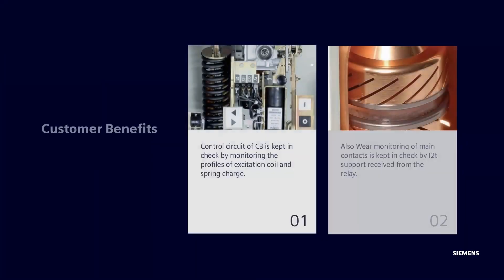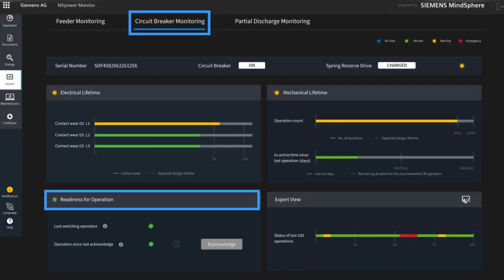As a result of the addition of the Expert View in Circuit Breaker Monitoring View, the control circuit of CB is kept in check by monitoring the profiles of excitation coil and spring charge. Also, monitoring of main contacts is kept in check by I2T support received from the relay. After every switching operation, analysis is done for the main contact as well as the control circuit of the circuit breaker, and the outcome of the analysis decides the readiness for the next operation.